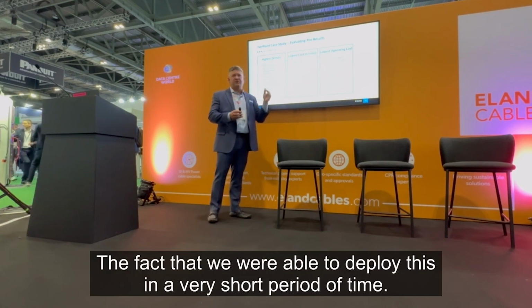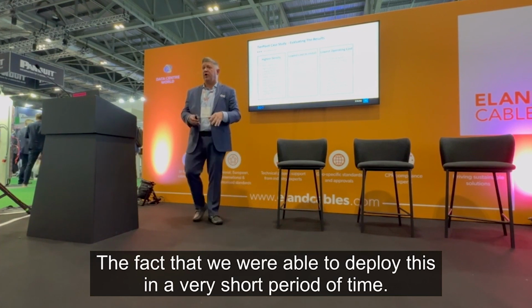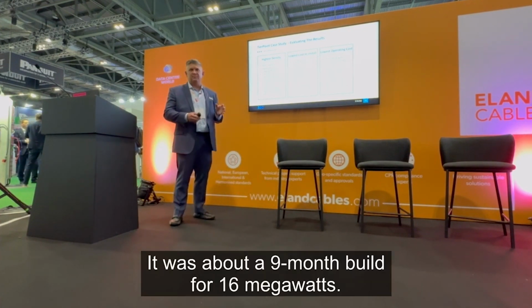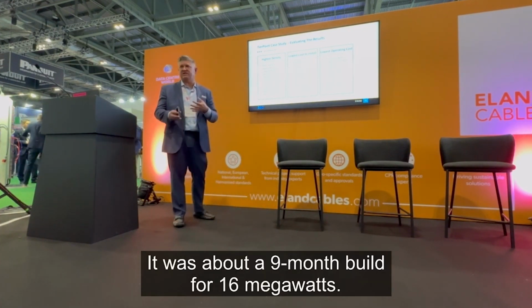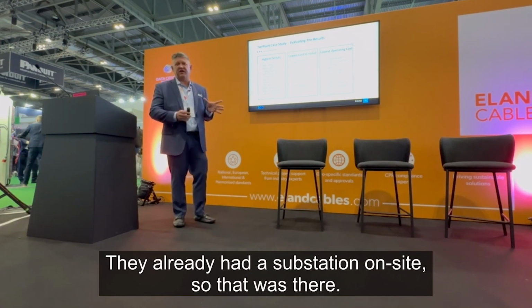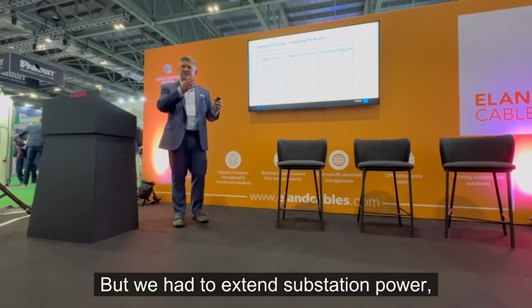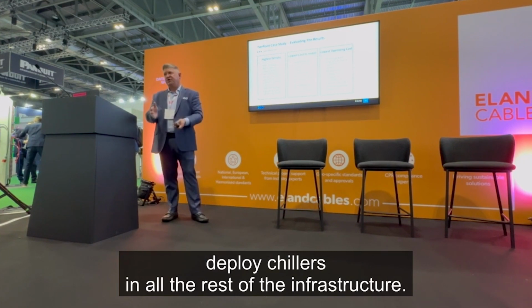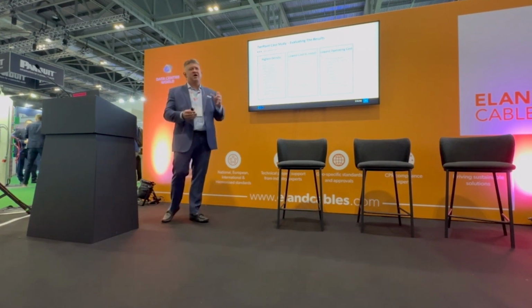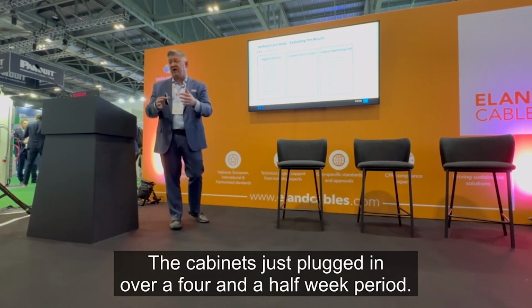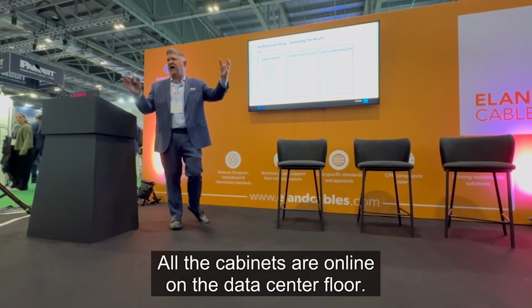And the fact that we were able to deploy this in a very, very short period of time - it was a 9-month build for 16 megawatts. We already had a substation on site, so that was there, but we had to extend substation power, deploy chillers, and all the rest of the infrastructure. The cabinets just kind of plugged in, and over about a 4.5-week period, all the cabinets were online with the data center floor.